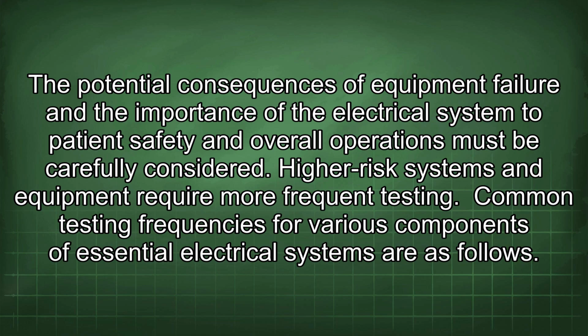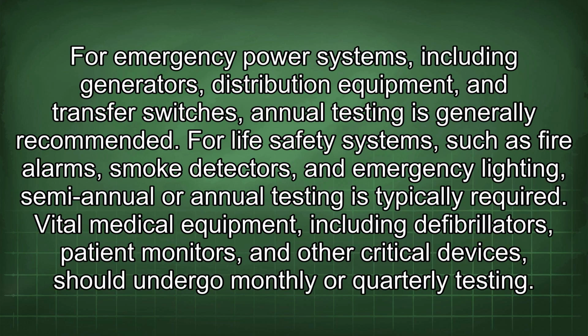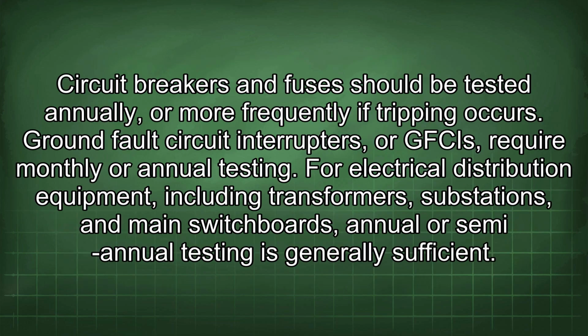Common testing frequencies for various components of essential electrical systems are as follows. For emergency power systems, including generators, distribution equipment, and transfer switches, annual testing is generally recommended. For life safety systems, such as fire alarms, smoke detectors, and emergency lighting, semi-annual or annual testing is typically required. Vital medical equipment, including defibrillators, patient monitors, and other critical devices, should undergo monthly or quarterly testing. Circuit breakers and fuses should be tested annually or more frequently if tripping occurs. Ground fault circuit interrupters, or GFCIs, require monthly or annual testing. For electrical distribution equipment, including transformers, substations, and main switchboards, annual or semi-annual testing is generally sufficient.